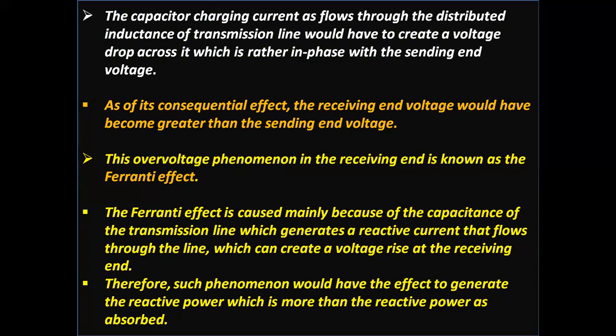The capacitor charging current, as it flows through the distributed inductance of the transmission line, creates a voltage drop across it which is in phase with the sending end voltage. As a consequence, the receiving end voltage becomes greater than the sending end voltage. That is the Ferranti effect. This overvoltage phenomenon at the receiving end is known as the Ferranti effect.